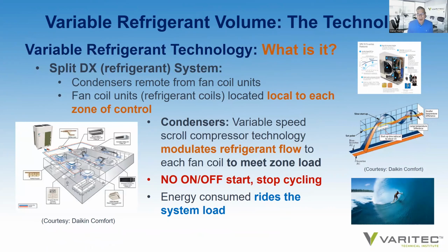So when we apply variable refrigerant technology to a building, what actually is it? You might be asking the question, how does it work? Well, first of all, it is a split DX refrigerant system. That is to say, the condensers that deposit the heat gain in the refrigerant gained within the building is deposited outdoors. That's the unit that actually dumps the heat energy secured by the refrigerant from the building and deposited outdoors. The indoor air handlers that offer the ventilation and the cooling coils are indoors, local to each zone. The package DX rooftop unit actually handles the total cooling load, both sensible load and latent load, at the cooling coil within the rooftop unit and uses air to transfer energy from a building.